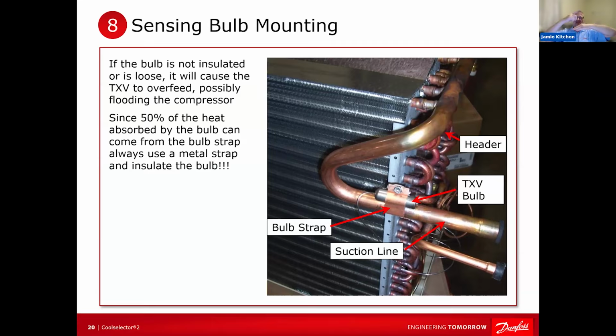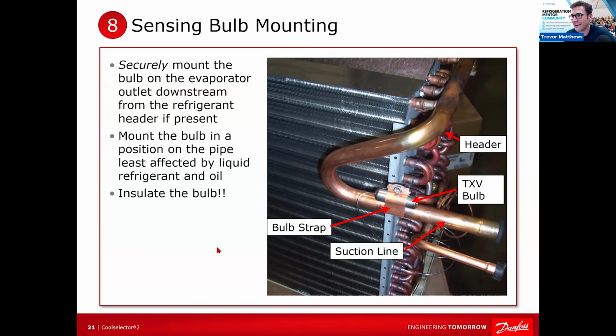Next thing is to wrap the insulation around it, okay? Zip ties and duct tape is not a good 2-in-1, all right? Make sure you use a metal bulb strap, it's tight, and insulate it, because on a properly operating system, half the heat or more that goes in the sensing bulb doesn't come from the pipe itself. It comes from the bulb strap that's wrapped around the entire pipe and over top of the entire sensing bulb. And it conducts heat and it's insulated. So you have this heat train that conducts from the pipe up into the bulb. That makes it far more reactive and efficient.